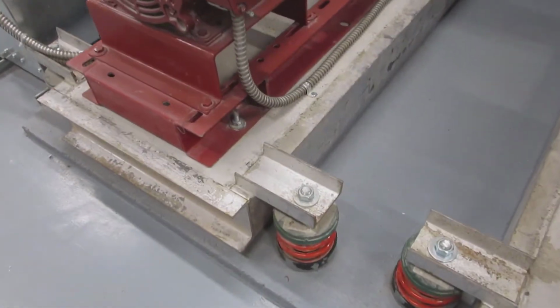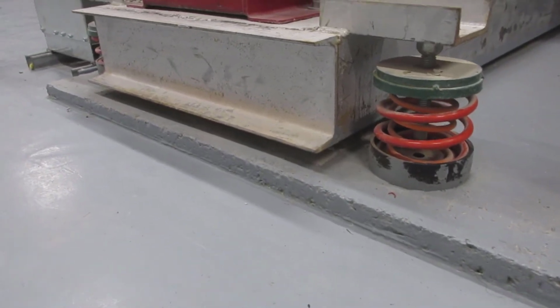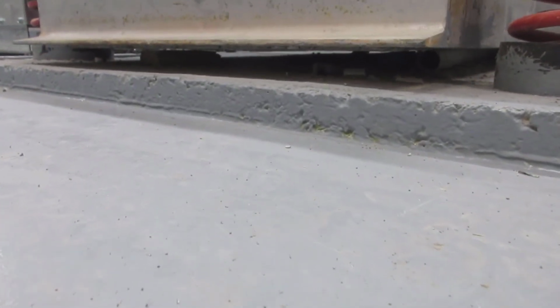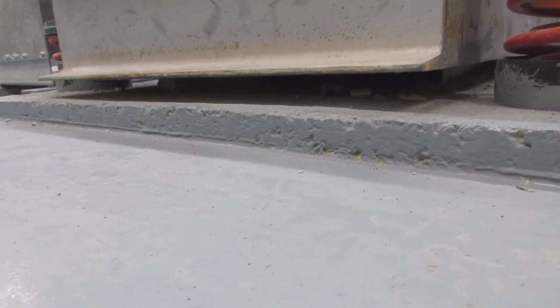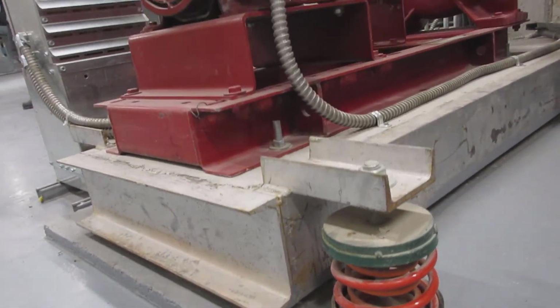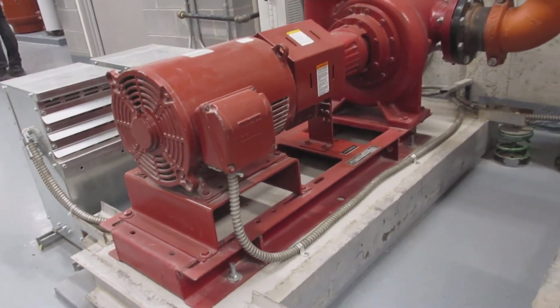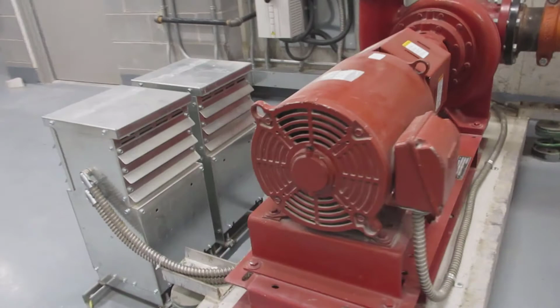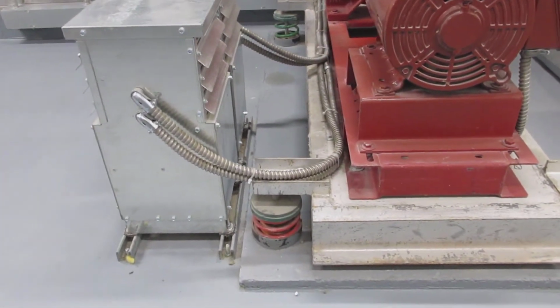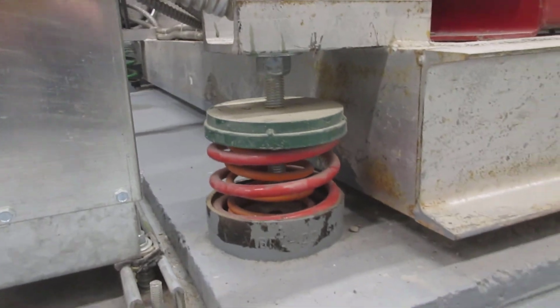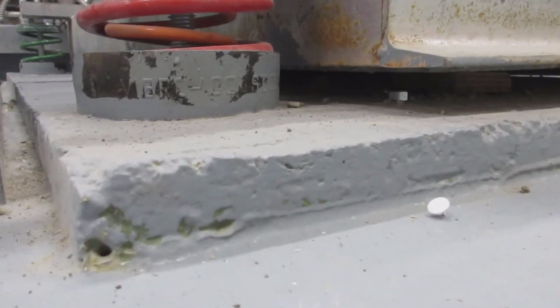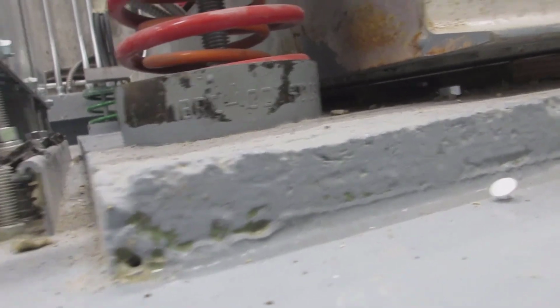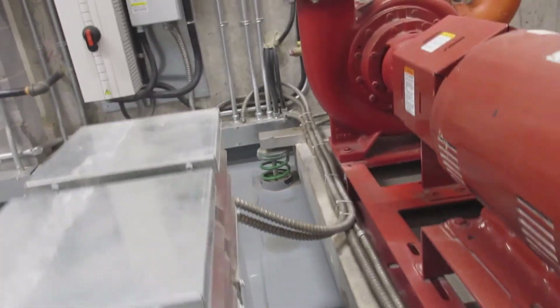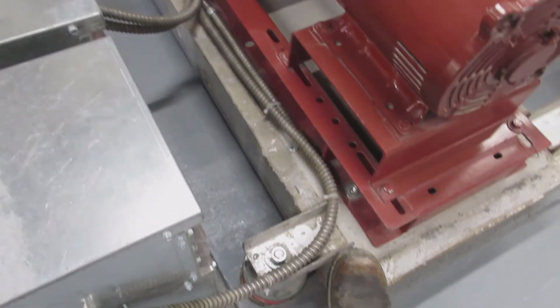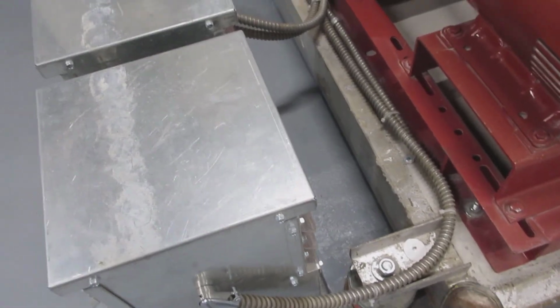Looking at the second pump, it appears to have more of a gap between the base and the floor, though not quite 2 inches. We can see some debris, though it's hard to tell if it's touching the base. This isolator appears to be adjusted and secured to the base. Notice all the flexible conduit. We'll talk about that a bit later. This corner isolator looks good, though the base is not quite 2 inches off the floor. I should have brought a flashlight to see underneath here. It's a little too dark, so we'll try to move the base and see what happens. I should have put the camera down to do this, but I was able to make the base move a little, so it appears to be floating.